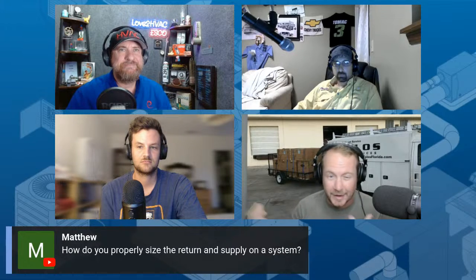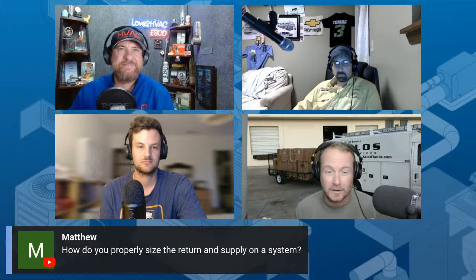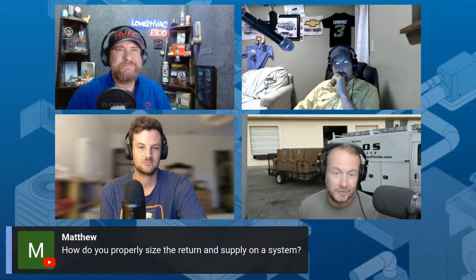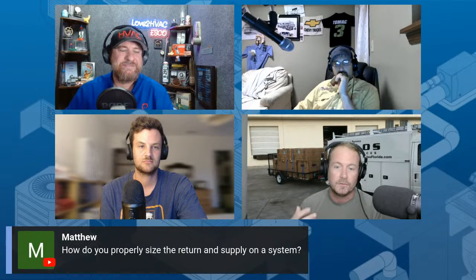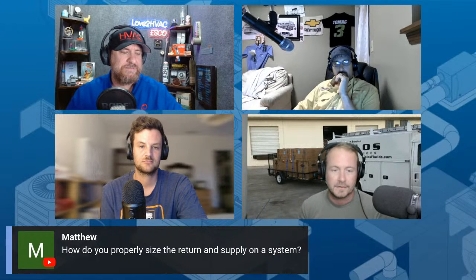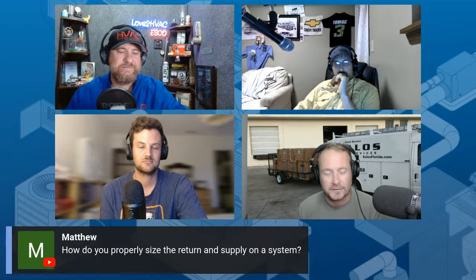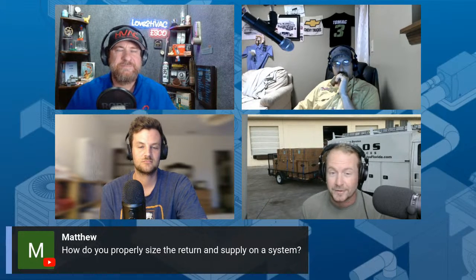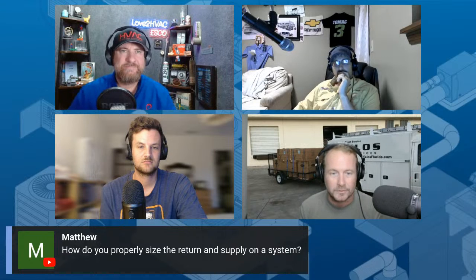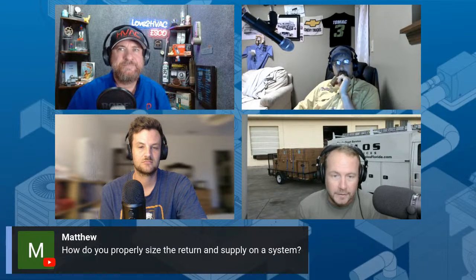We're talking about field assessment here, where you're in the field trying to figure out, hey, what's the velocity? First you need to know what airflow this system should be producing, which is a pretty big ask. Then you calculate based on the size of this duct. That's field assessment. If you want to size it properly, as in you're designing a system, then you need to use Manual D. That's currently the way to do it.